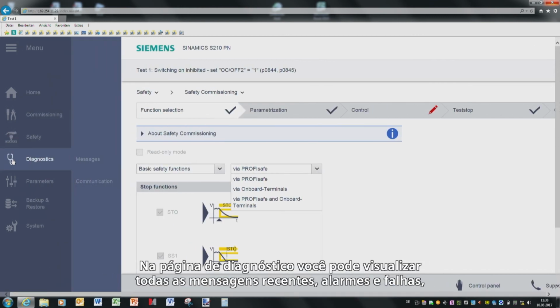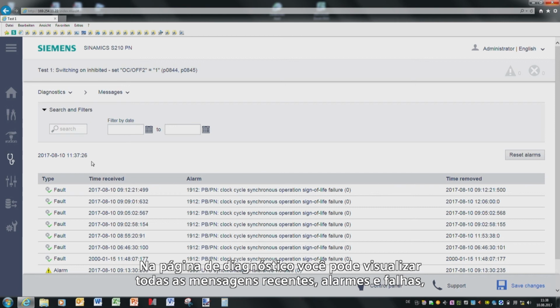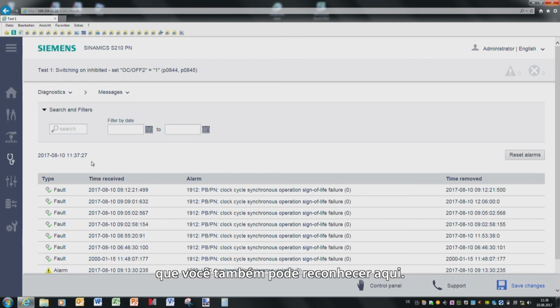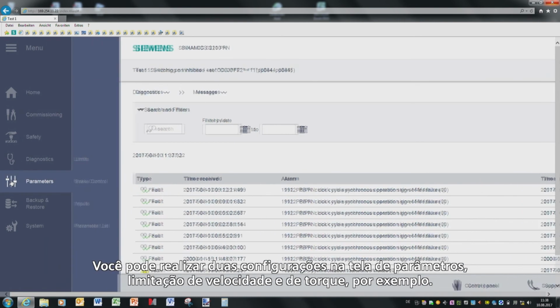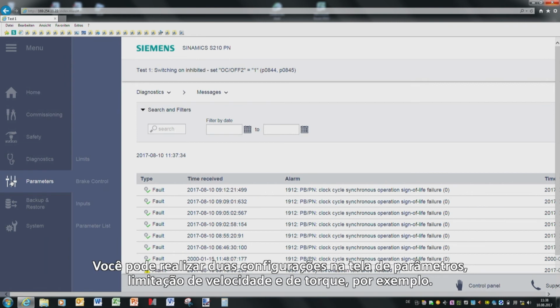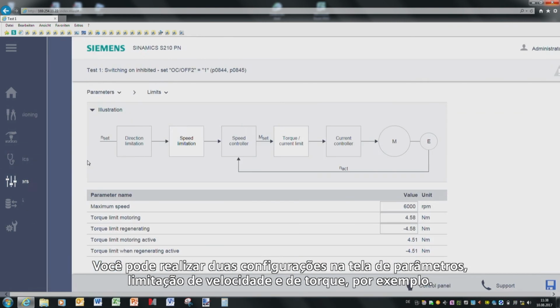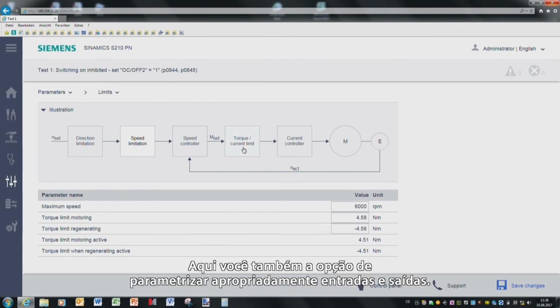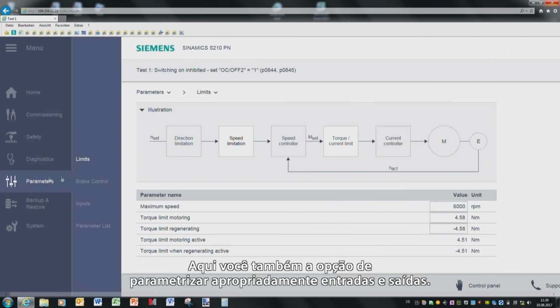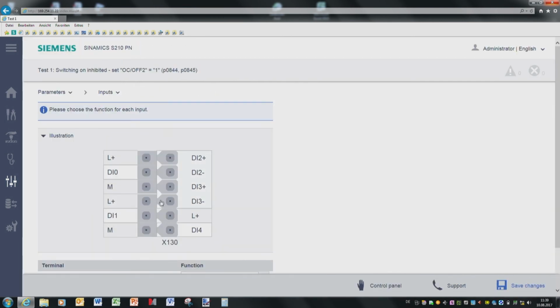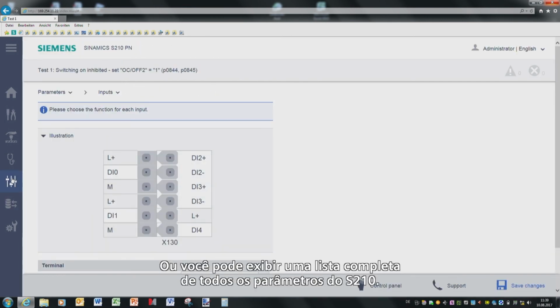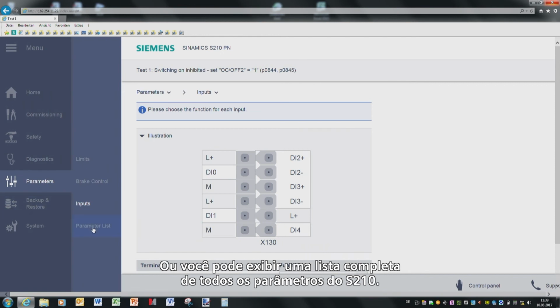On the diagnostics page, you can see all of the actual messages, alarms, and faults, which you can also acknowledge here. You can make settings in the parameter screen form, speed and torque limits, for example. Here, you also have the option of appropriately parameterizing inputs and outputs. Or you can display a complete list of all of the S210 parameters.